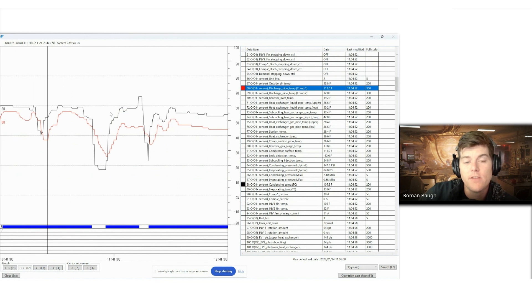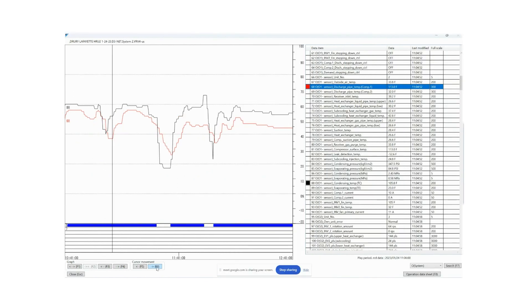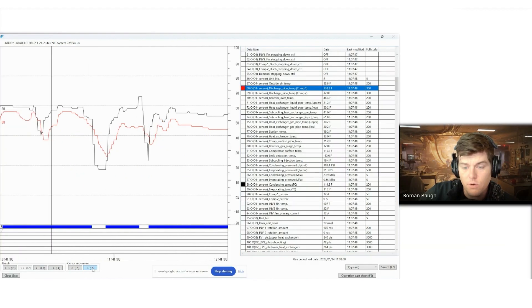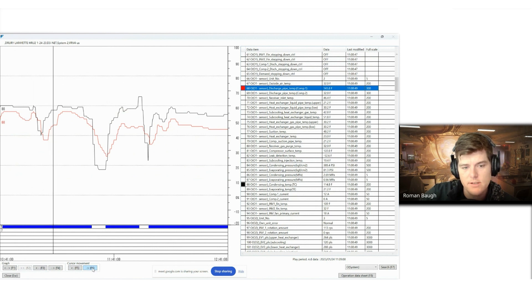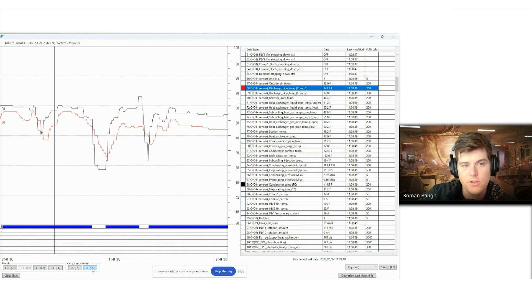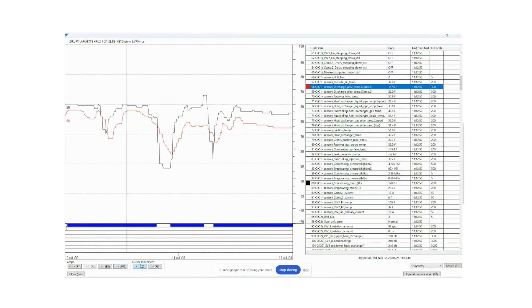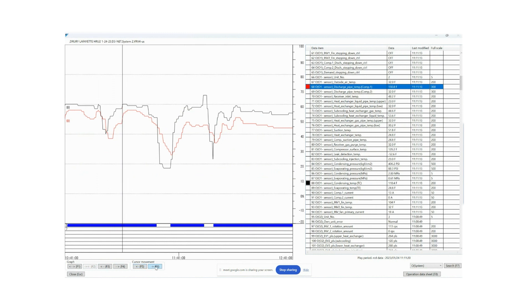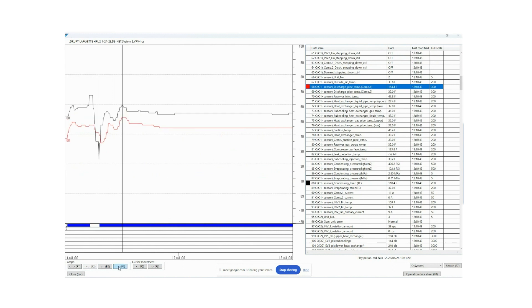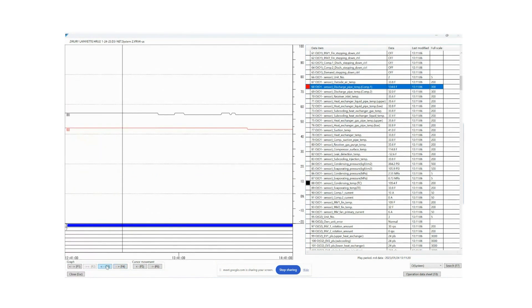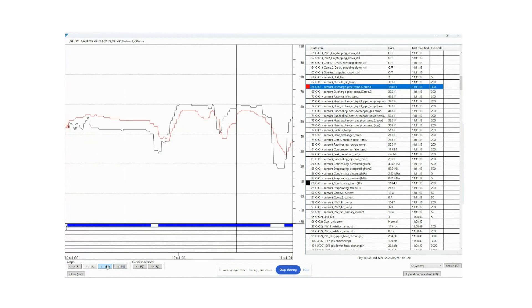So that's how you navigate the graph on the left hand side. You'll notice I can move in small increments of recording sections every 20 seconds here. Someone set this up to record every 20 seconds. It's not that the data changed in those 20 seconds. Data updates every 60 seconds. So if you want to save yourself a bunch of extra clicks when you're looking at service checker data, just make sure you set that record up correctly. And then from there, I can navigate inside this window and graph using these arrow buttons on the bottom left. That lets me go through the data points here and also scroll in a fine-tuned manner. But then also I can jump over to another section of data by clicking these buttons, these left and right arrows, the F3 and F4. This lets me go through the rest of the data that I'm looking at.